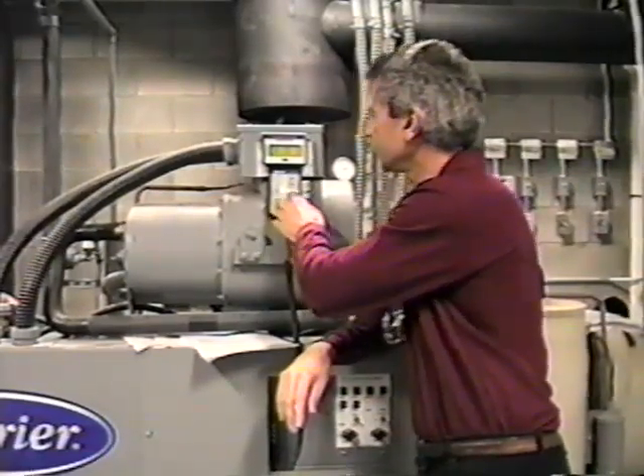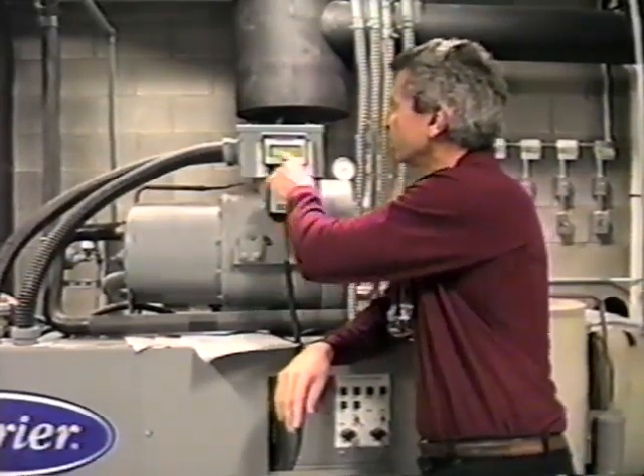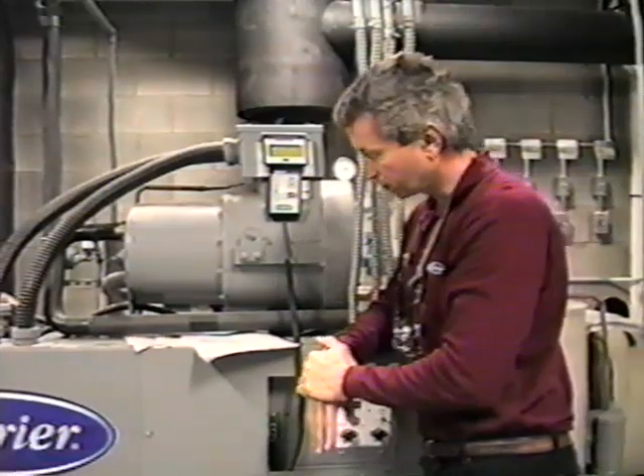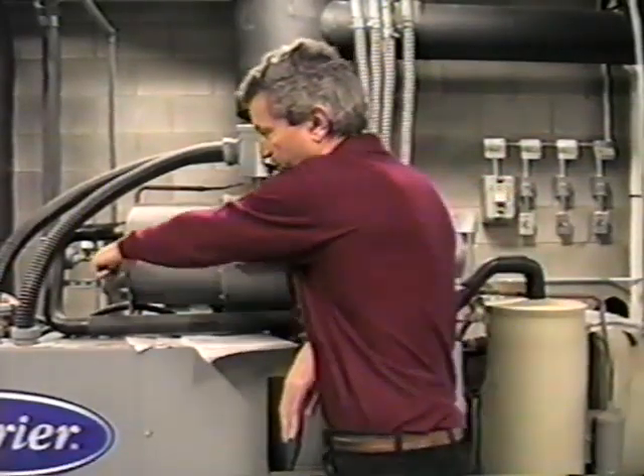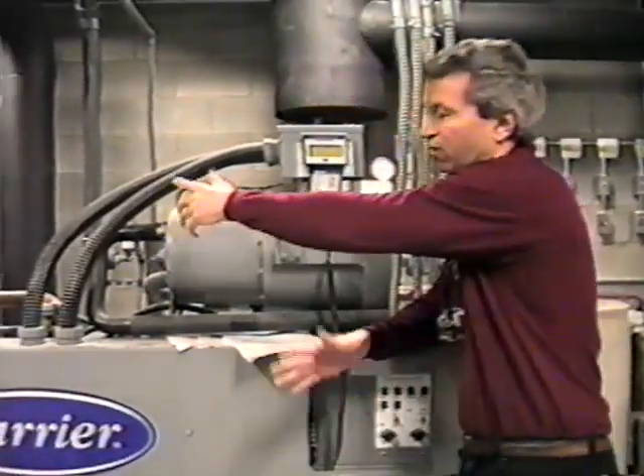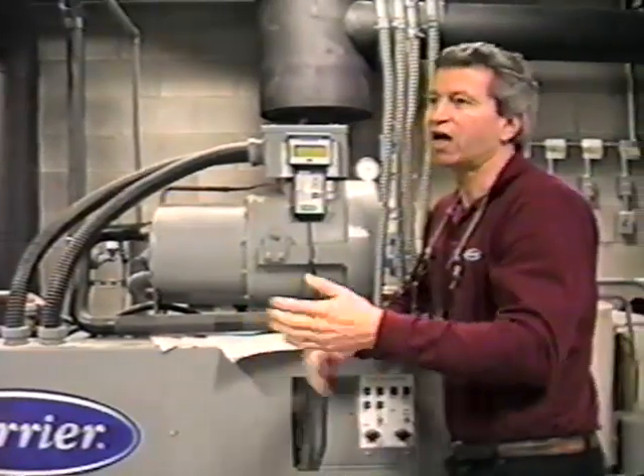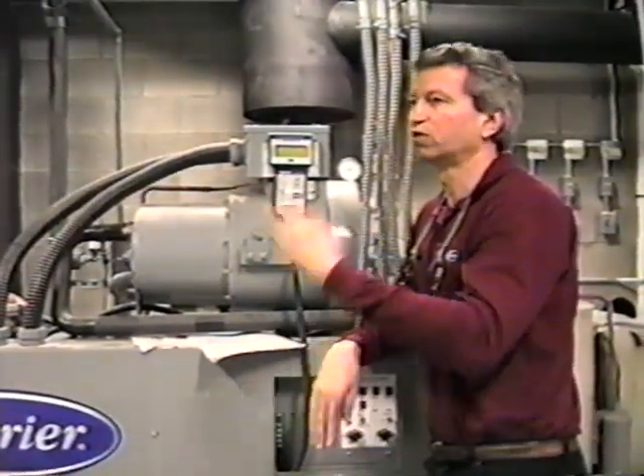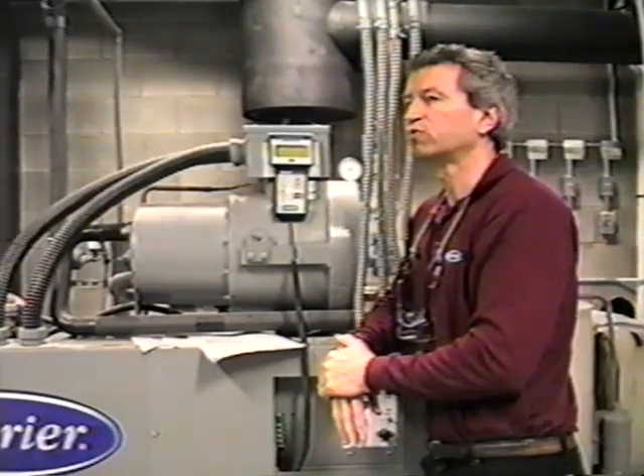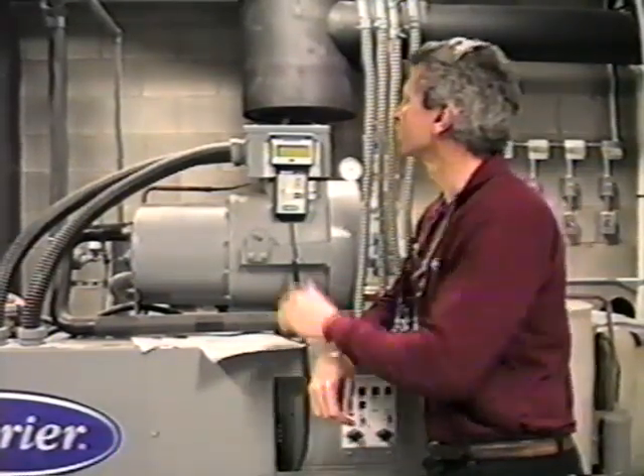You have MLV, if you expand on that, minimum load valve, and that's essentially, we call it minimum load control. It's essentially a hot gas bypass that allows you to run in the lower capacity ranges without cycling the machine.